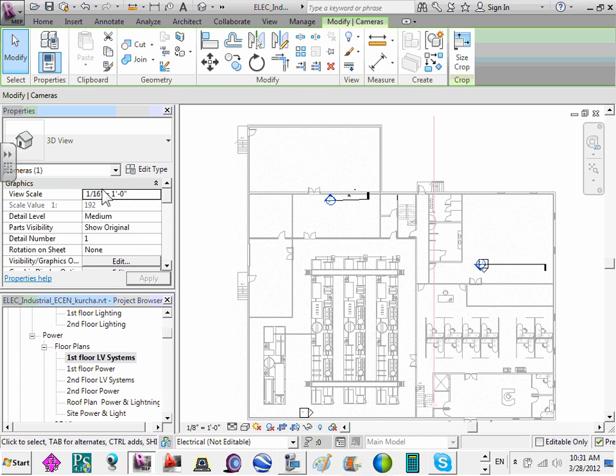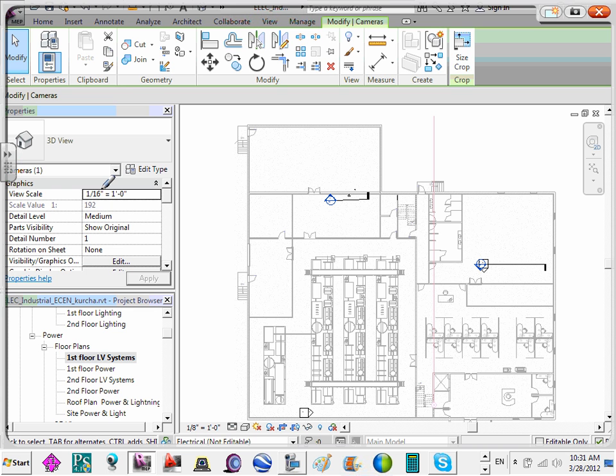Everything's going to be, the fire alarm system's going to be cross zone, but that's a separate system if it's a chemical releasing system, chemical agent system. So there they're talking about the preaction. When you're talking about the preaction system in the data center, what they say when they're talking about cross-zoning systems is you're going to have, say, five smoke detectors, and you're going to have two zones going in here.